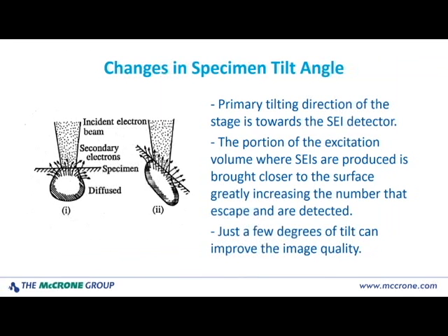In the SEM, we also have the option of tilting the sample to improve it. On the far left, we have our surface of our sample normal to our beam, and the beam is impinging into it forming a normal excitation volume. But if we take our sample and tilt it — or take our stage, if you have this capability — then what happens is the excitation volume is brought closer to the surface. Because it's brought closer to the surface, now the region generating secondary electrons produces more secondary electrons. So they have less solid material to pass through. We have artificially pulled this excitation volume closer. Just a few degrees of tilt can make an amazing difference in your image quality. If you don't have a tilting stage, just take your substrate and configure some way to put something under one side of it and tilt it over a little bit.